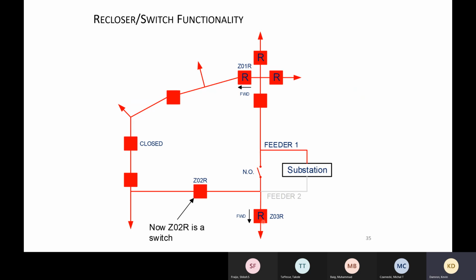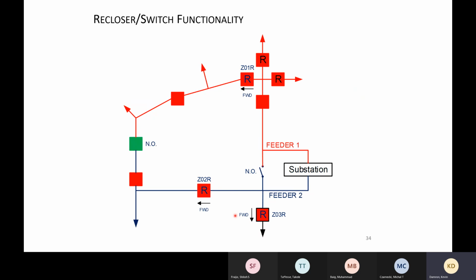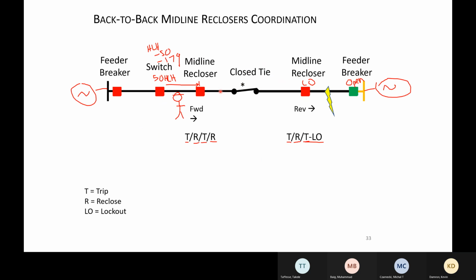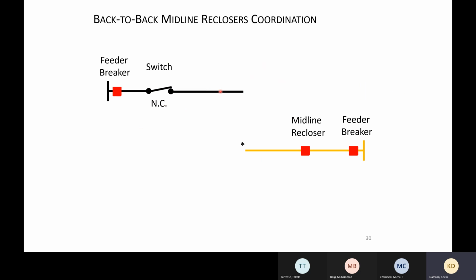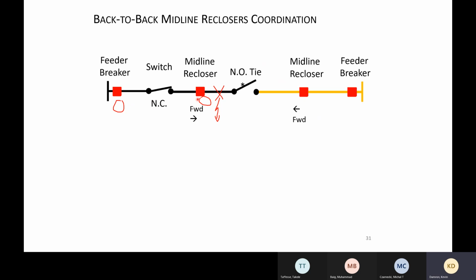The other thing I talked about was slapping conductors. Let me go back to the normal one. I've got my station breaker back here. If I have a fault past Z01R on this lateral, you may have Z01R and the station breaker both trip. And we've had instances where they both tripped, they both reclosed, and then the station breaker tripped to lockout.